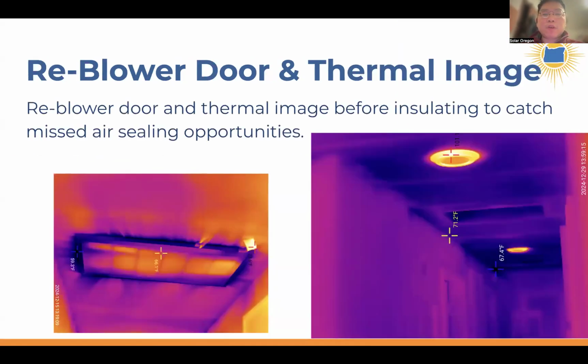When you think you're done with air sealing, it behooves you to have a second blower door test, blower dooring and thermal imaging again to catch any missed air sealing opportunities. As you can see, it's a dramatic difference once that return plenum was air sealed, between the left and right thermal image.